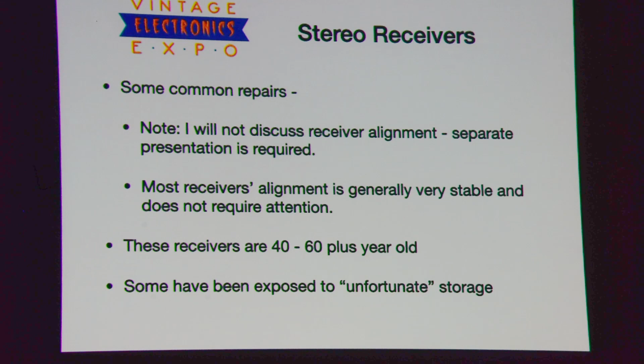Electrolytic capacitors, let's talk about that. That is a really common failure point, and they fail with age. Electrolytics are called dry capacitors, but they really aren't dry. So one failure mode is that the electrolyte simply dries out. The moisture escapes, depending on how well sealed it was, and the older it is, the less likely it was to be well sealed. They will develop leakage, go open because it dried out altogether, or worse yet, they'll short unexpectedly.